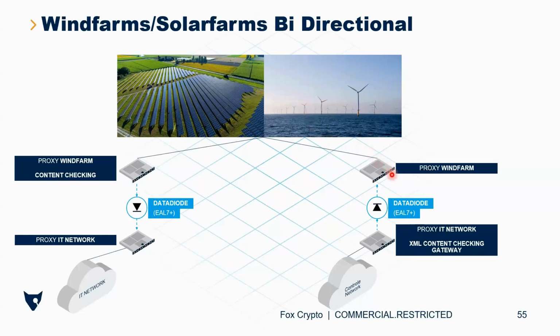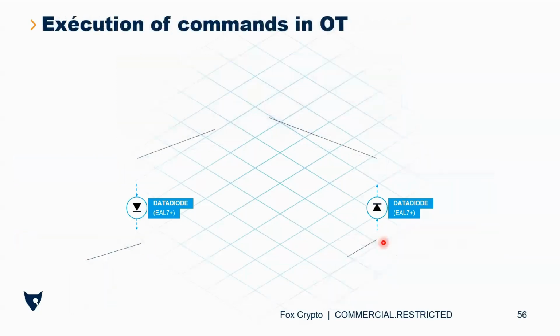And then we sat down with their CISO and we said, okay, you can do bi-directional, but you need to make sure that these two networks will never be connected, because then you've got a loop and a hacker has an option to get in. And he said, no, I will make sure that this happens in one room, physical room only. And once the upgrade is done, I'll switch it off physically, no power. And via that approach, you see suddenly that the industry is becoming security aware, and they're willing to take steps. And then there are options.